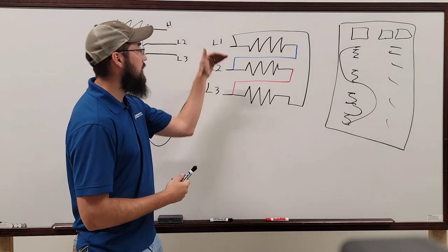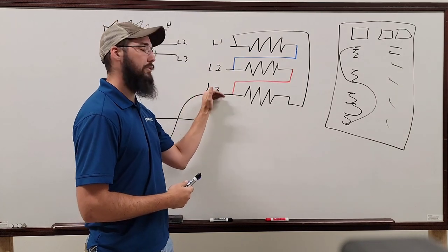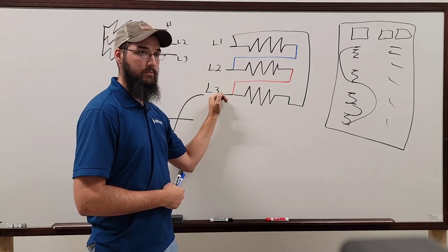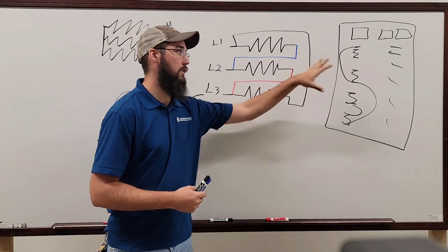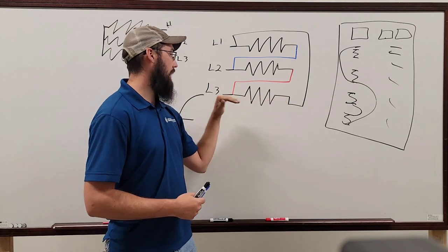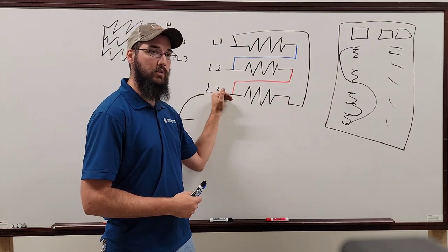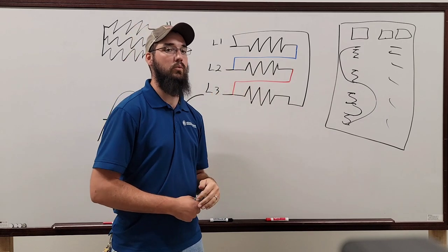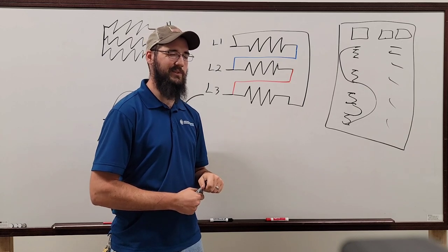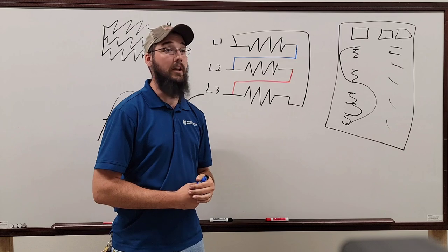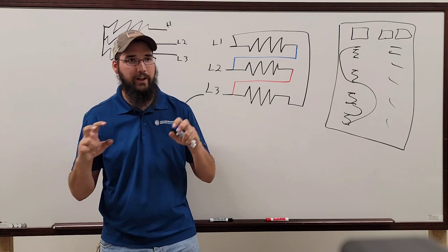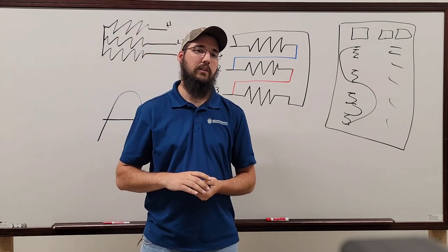So part of what he's saying is, you'll walk up to some of these and L3, for example, these may be pulling 20 amps, 20 amps, this one will be pulling 30. It's because of having multiple heats and stages, the way it gets wired in, it adds additional load to that one particular leg over the other two. So instead you're using it as a junction for more heaters, basically? Basically. But a single phase heater. All those are single phase. There's no three phase. All tied together, three single phases.